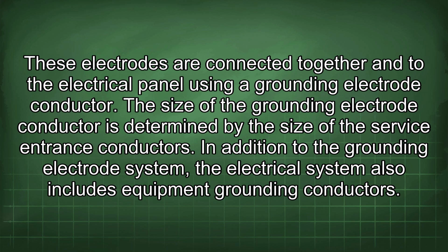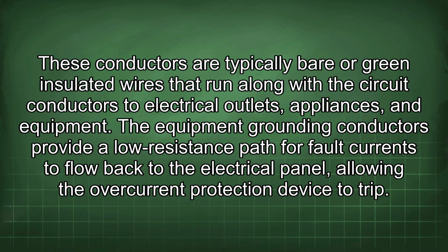In addition to the grounding electrode system, the electrical system also includes equipment grounding conductors. These conductors are typically bare or green insulated wires that run along with the circuit conductors to electrical outlets, appliances, and equipment. The equipment grounding conductors provide a low resistance path for fault currents to flow back to the electrical panel, allowing the overcurrent protection device to trip.